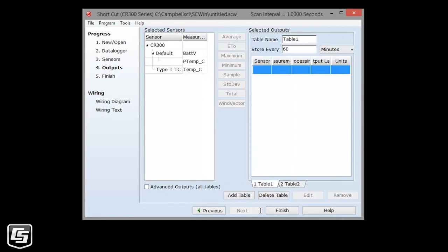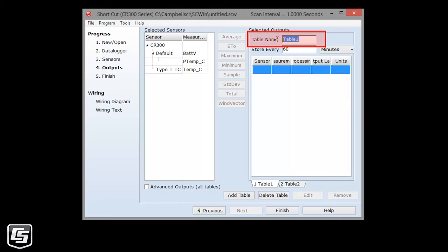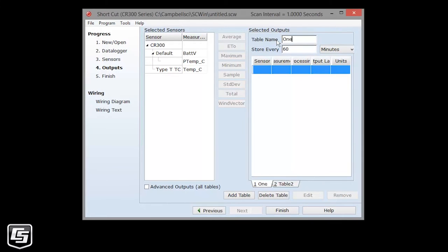This is the output section where you will specify the data that you want stored and later copied to your computer. This is the information that you need to do your job, one of the reasons you have a data logger. Enter a name for the first table. The name needs to start with a letter and has to be eight characters or less. In CRBasic, you can use longer names. I'll call mine One.